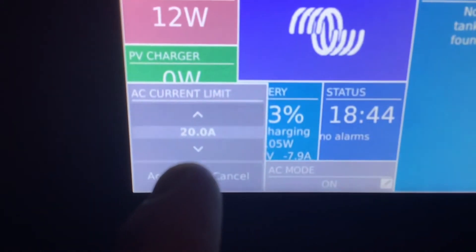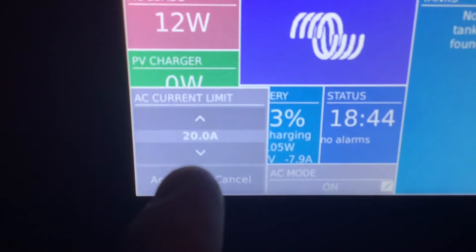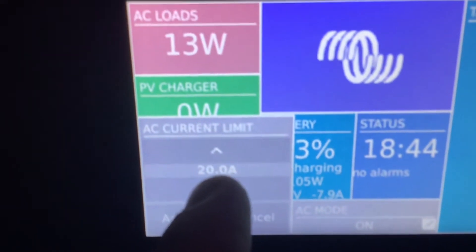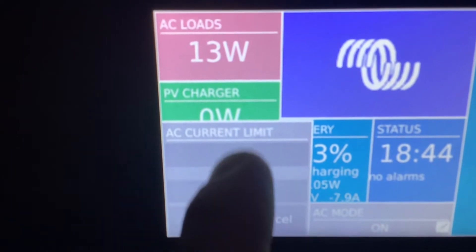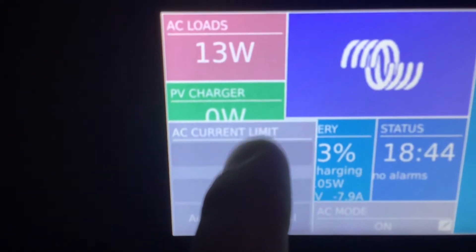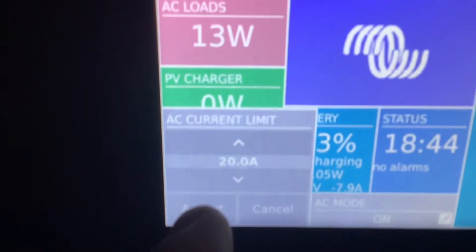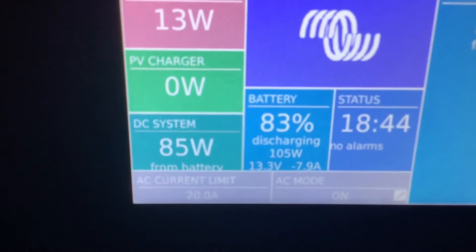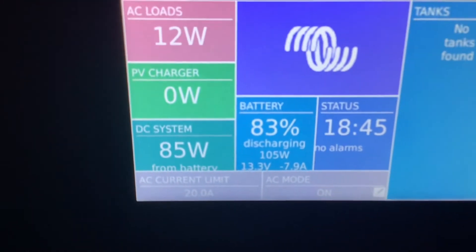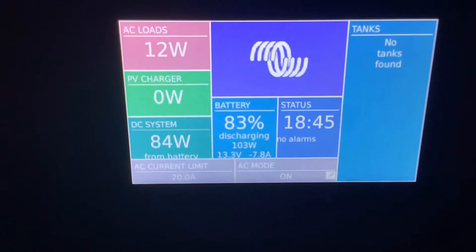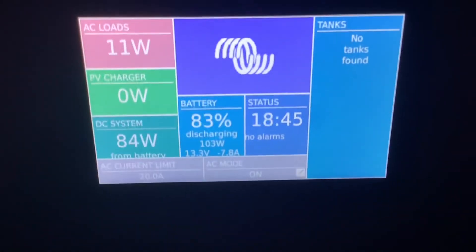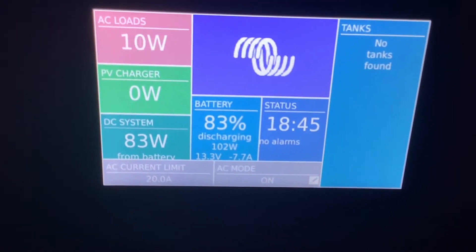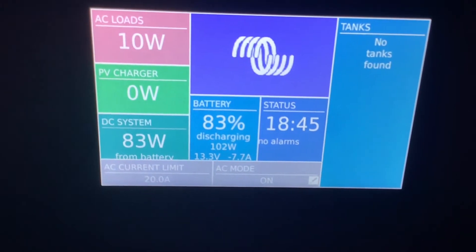If you look here, it says AC current limit — you want to set this to whatever shore power you're plugged into. If it's a 15 amp or 20 amp household receptacle, set it to 15 or 20. If it's a 30 amp or 50 amp campground plug-in, set it to 30 or 50. If you have a smaller generator, set it to 25 or lower. If you have a larger generator, set it to 45 or lower.